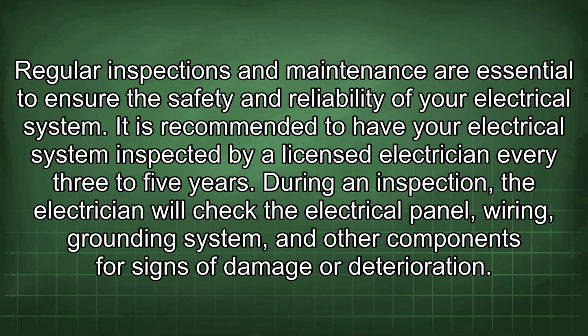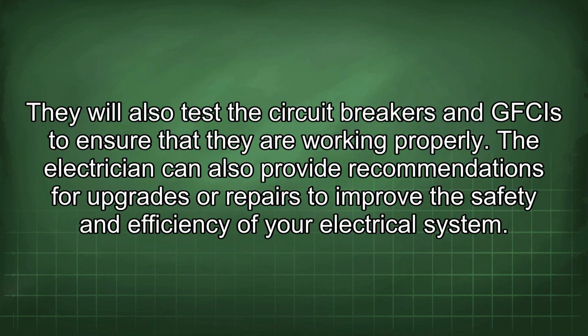Regular inspections and maintenance are essential to ensure the safety and reliability of your electrical system. It is recommended to have your electrical system inspected by a licensed electrician every 3 to 5 years. During an inspection, the electrician will check the electrical panel, wiring, grounding system, and other components for signs of damage or deterioration. They will also test the circuit breakers and GFCIs to ensure that they are working properly. The electrician can also provide recommendations for upgrades or repairs to improve the safety and efficiency of your electrical system.